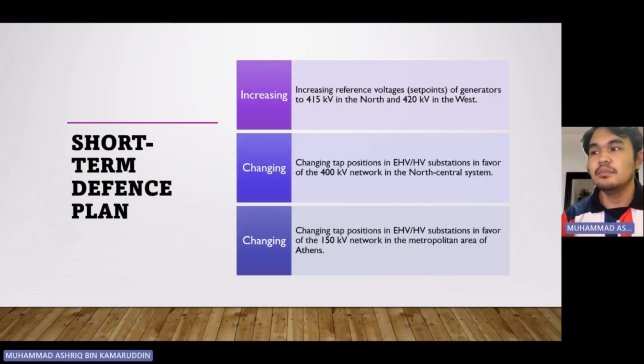For the short-term defense plan, it will involve increasing reference voltage set points of generators to 415 kV in the north and 420 kV in the west.